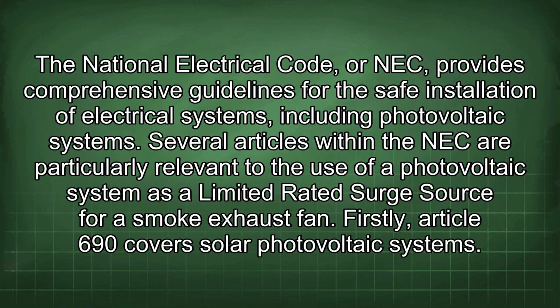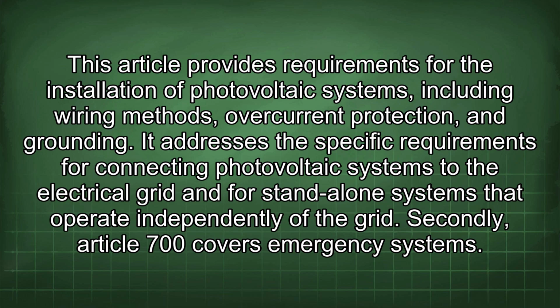The National Electrical Code, or NEC, provides comprehensive guidelines for the safe installation of electrical systems, including photovoltaic systems. Several articles within the NEC are particularly relevant to the use of a photovoltaic system as a limited rated surge source for a smoke exhaust fan. Firstly, Article 690 covers solar photovoltaic systems. This article provides requirements for the installation of photovoltaic systems, including wiring methods, overcurrent protection, and grounding.